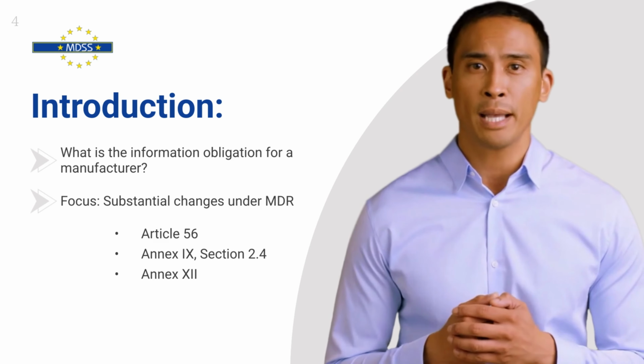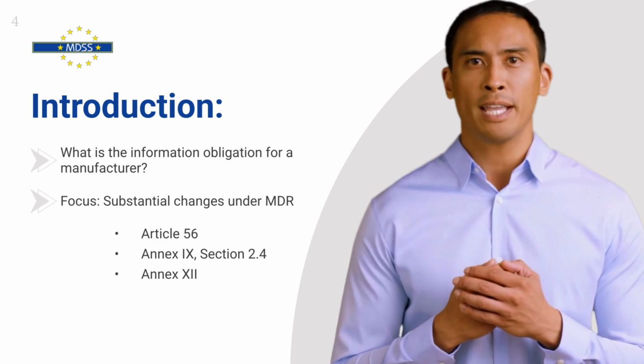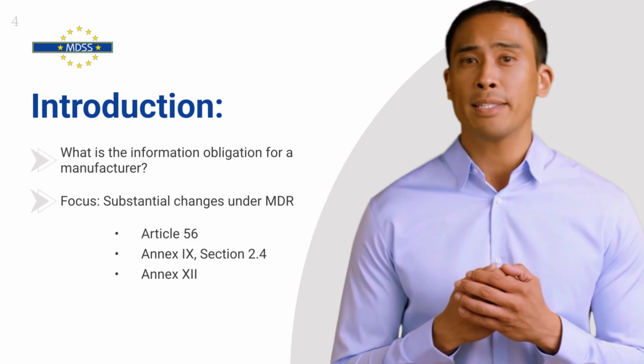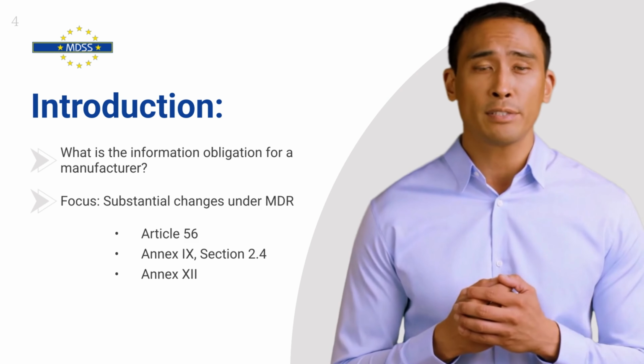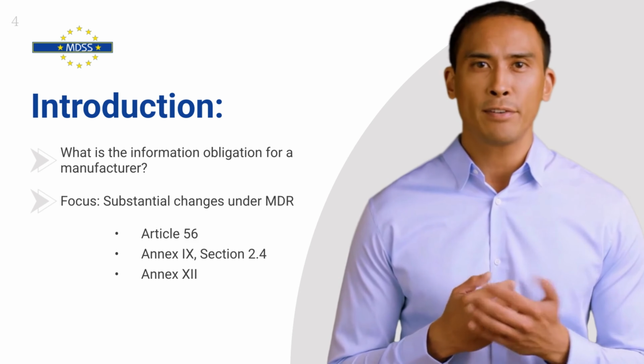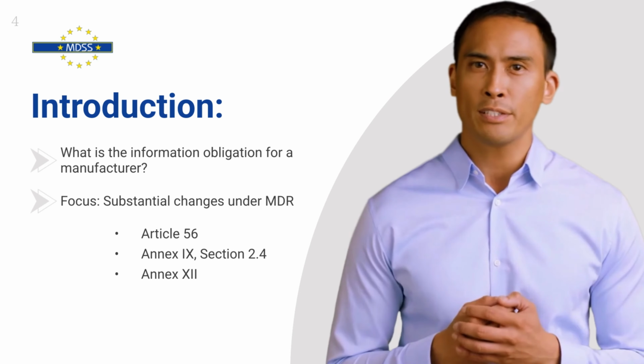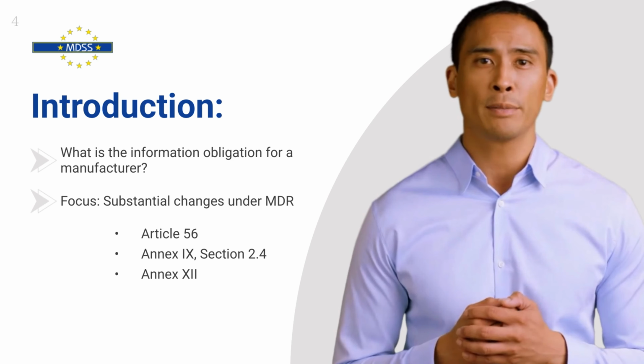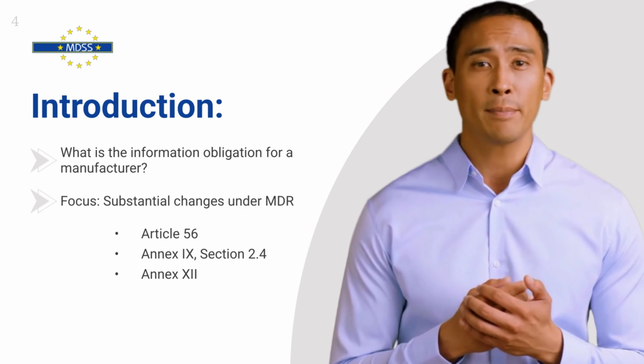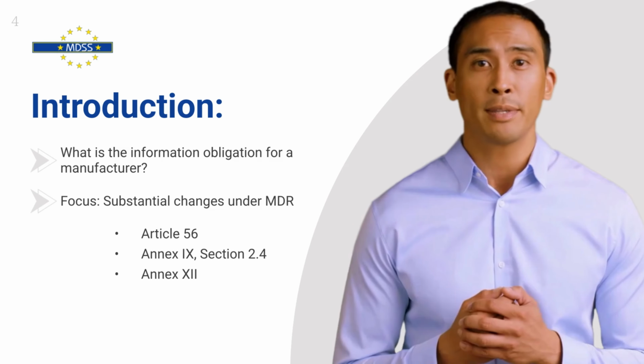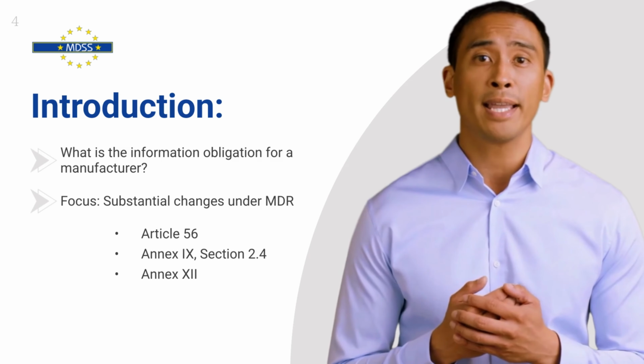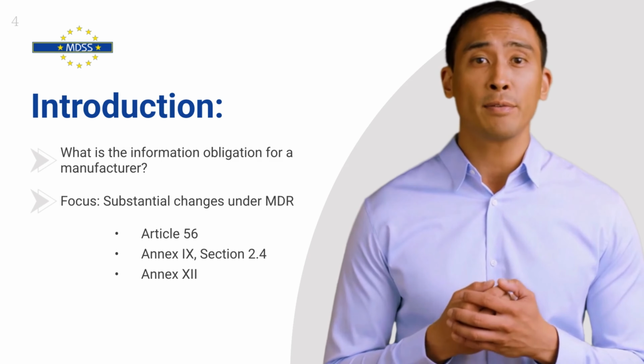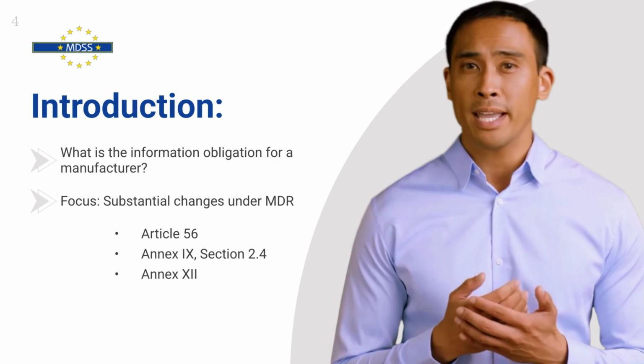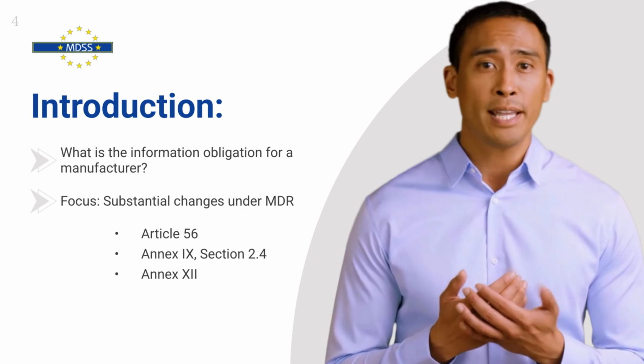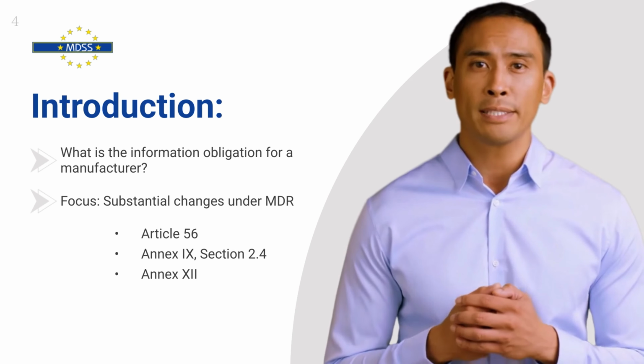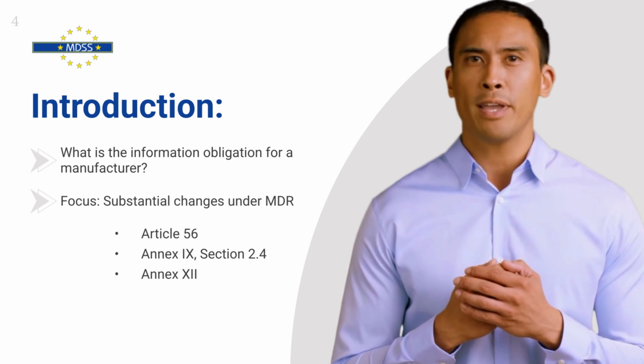in such a manner. In fact, the obligation to assess whether a change is substantial lies primarily with the manufacturer. It is the manufacturer's duty to determine whether the notified body must be informed as part of the conformity assessment procedure that has been approved. The notified body's responsibility is to ensure that the approved quality management system provides for the procedures that the manufacturer informs the notified body of planned substantial changes. Then, the responsibility of the notified body starts again after it has been notified of the planned substantial change. At that point, its obligations are clearly outlined by the regulation for the notified body.